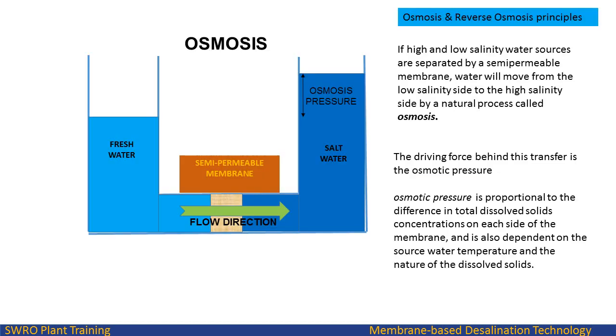If high and low salinity water sources are separated by a semi-permeable membrane, water will move from the low salinity side to the high salinity side by a natural process called osmosis. The driving force behind this transfer is the osmotic pressure. This pressure is proportional to the difference in total dissolved solids concentrations on each side of the membrane, and is also dependent on the source water temperature and the nature of the dissolved solids.